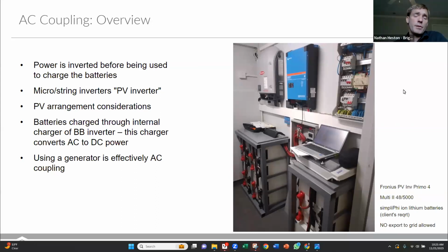That's a great point, Daniel, and thank you for going into more detail and clarifying why you want to use AC coupled, right? And the other reason for AC coupled systems is there historically has been a good agreement with the grid for AC coupled systems, right? So you install AC coupled solar, you send power out to the grid, you don't have batteries, right? And you get compensated for that.